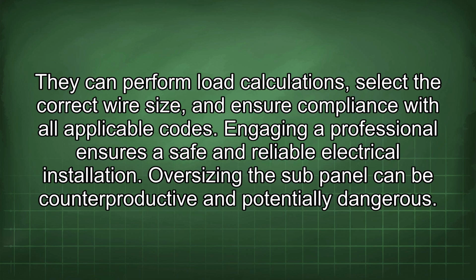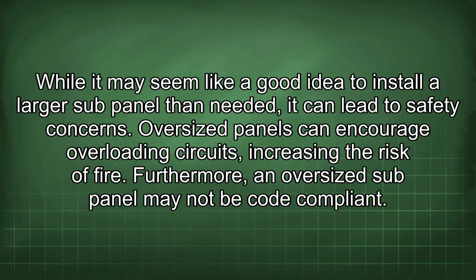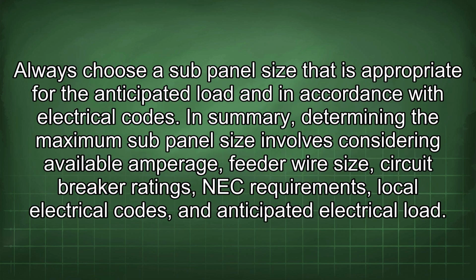Oversizing the sub-panel can be counterproductive and potentially dangerous. While it may seem like a good idea to install a larger sub-panel than needed, it can lead to safety concerns. Oversized panels can encourage overloading circuits, increasing the risk of fire. Furthermore, an oversized sub-panel may not be code compliant. Always choose a sub-panel size that is appropriate for the anticipated load and in accordance with electrical codes.